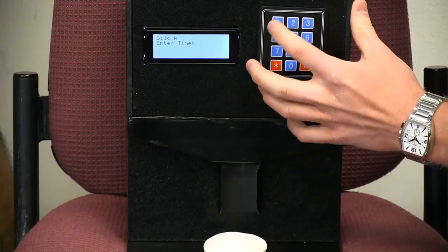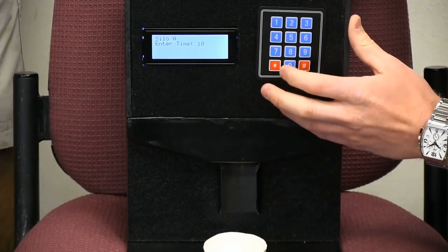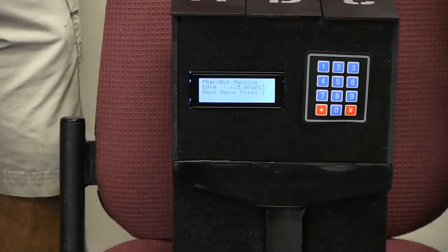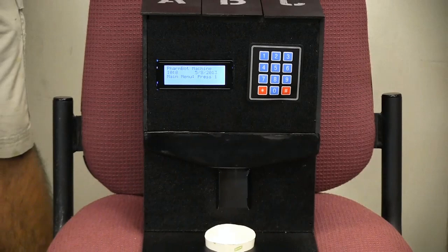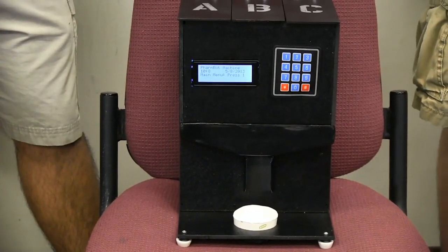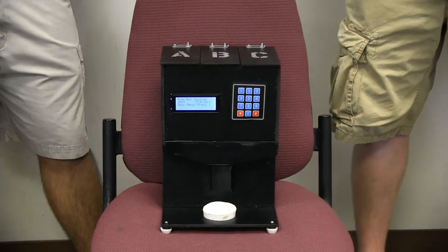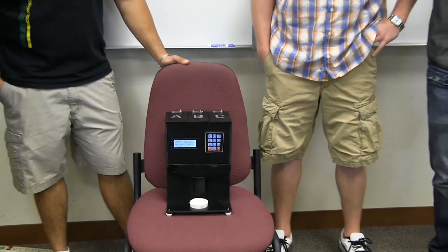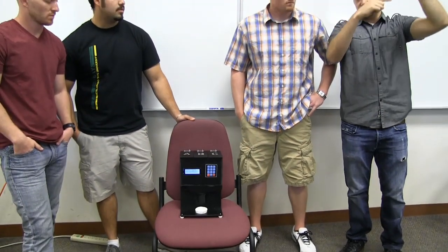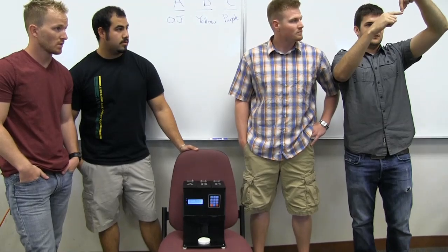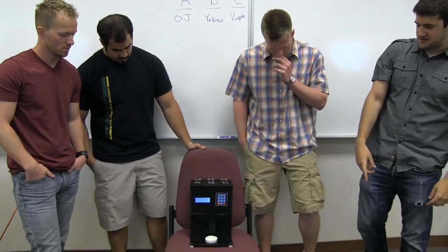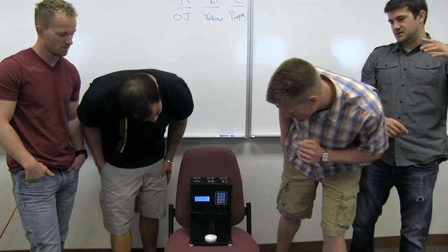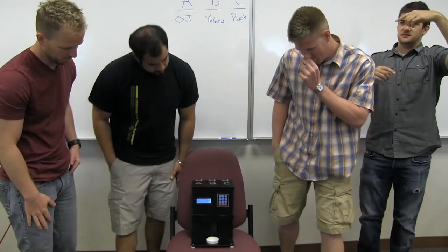Basically, what happens when a pill gets dispensed is we have a silo that's a funnel, and at the bottom of the funnel there's a solenoid that blocks all the pills from coming down. When the time is correct, the solenoid fires, allowing a pill to drop, and then it pushes out the front down into our cup. There's an infrared beam going across the bottom of the machine.